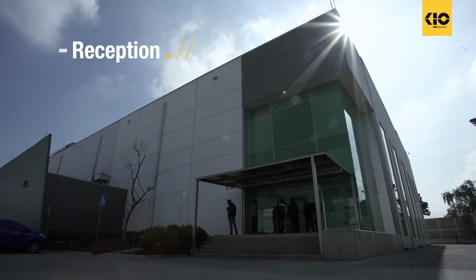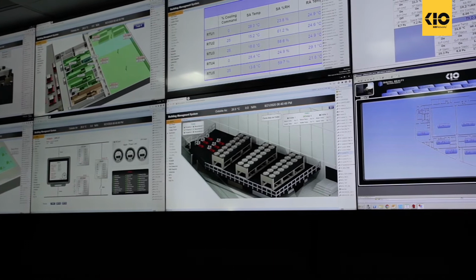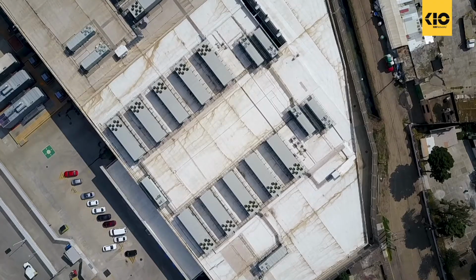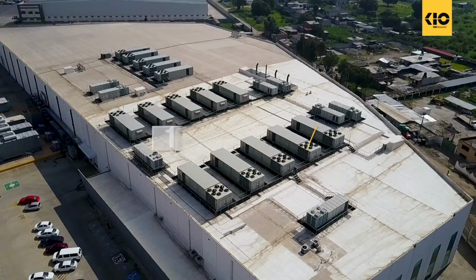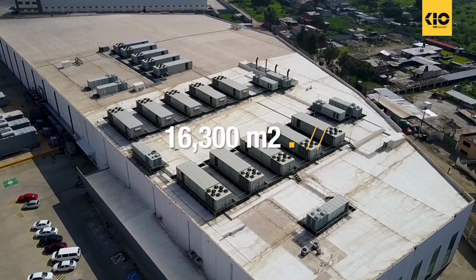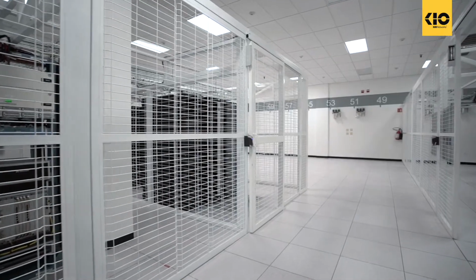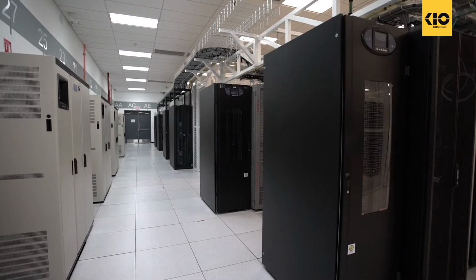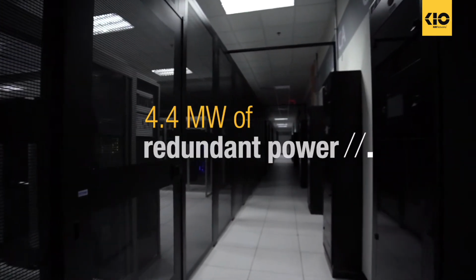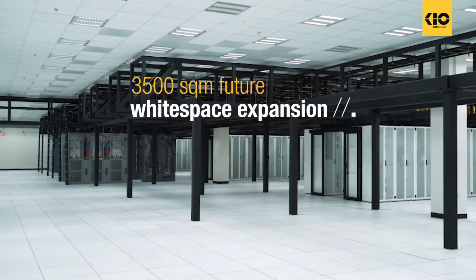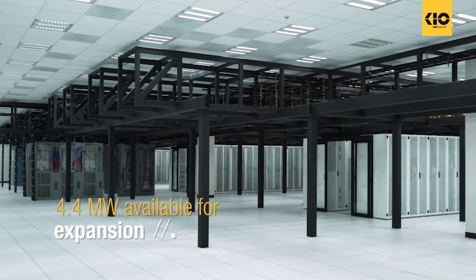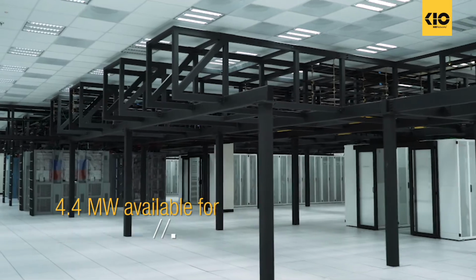We will show you the infrastructure and critical systems we have. This data center has 27,000 square meters of land and 16,300 square meters of construction. Data center current active white space is 4,000 square meters, 4.4 megawatts of redundant power. Another 3,500 square meters, 4.4 megawatts, are available for future white space expansion.